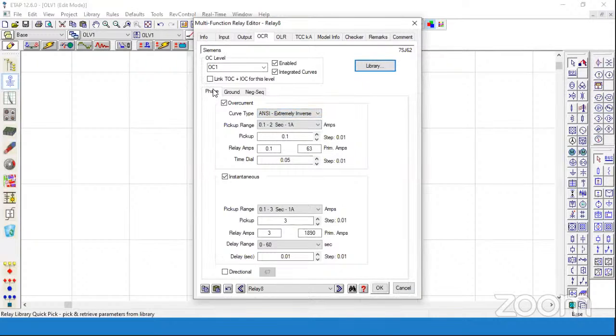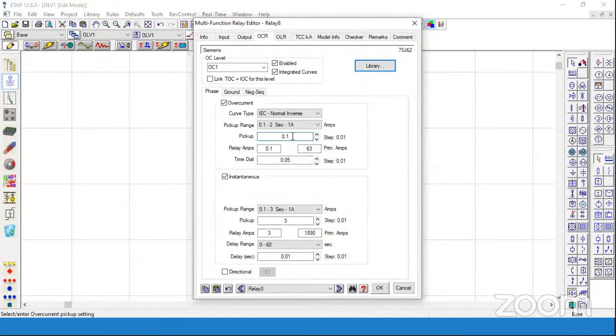Now here there are certain parameters we need to set in ETAP after certain calculations. After calculating the relay settings, we need to input these parameters for the relay for relay coordination. The settings we need to give in this section.